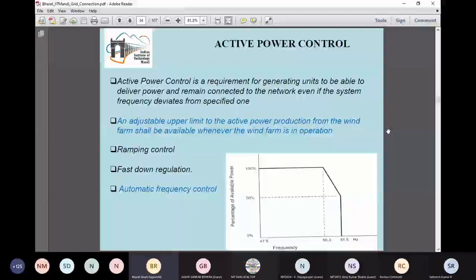But some of the researchers are offering a solution. The first solution is that the wind turbine system has inertia, and whenever more active power is required, this moving inertia can be utilized momentarily to get more energy and feed it into the grid if the frequency is low. So this is how an extra amount of renewable energy can be obtained for participation in the frequency control.